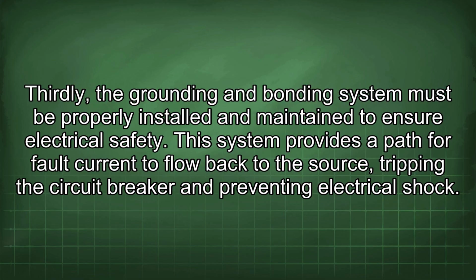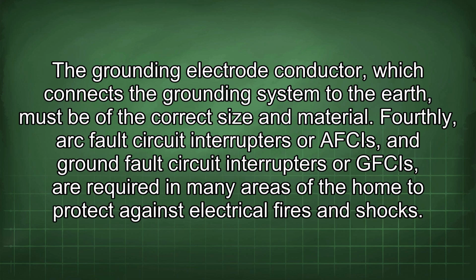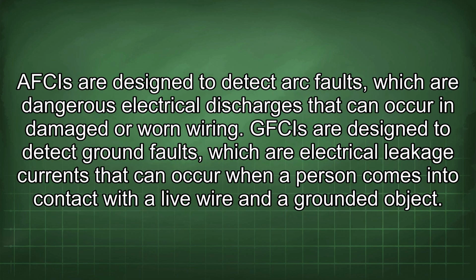This system provides a path for fault current to flow back to the source, tripping the circuit breaker and preventing electrical shock. The grounding electrode conductor, which connects the grounding system to the earth, must be of the correct size and material. Fourthly, arc fault circuit interrupters or AFCIs and ground fault circuit interrupters or GFCIs are required in many areas of the home to protect against electrical fires and shocks. AFCIs are designed to detect arc faults, which are dangerous electrical discharges that can occur in damaged or worn wiring. GFCIs are designed to detect ground faults, which are electrical leakage currents that can occur when a person comes into contact with a live wire and a grounded object.